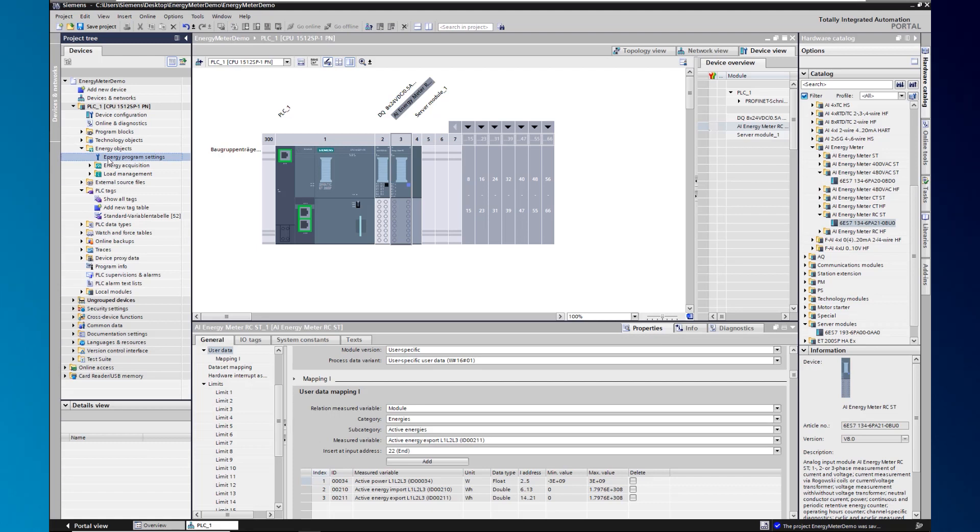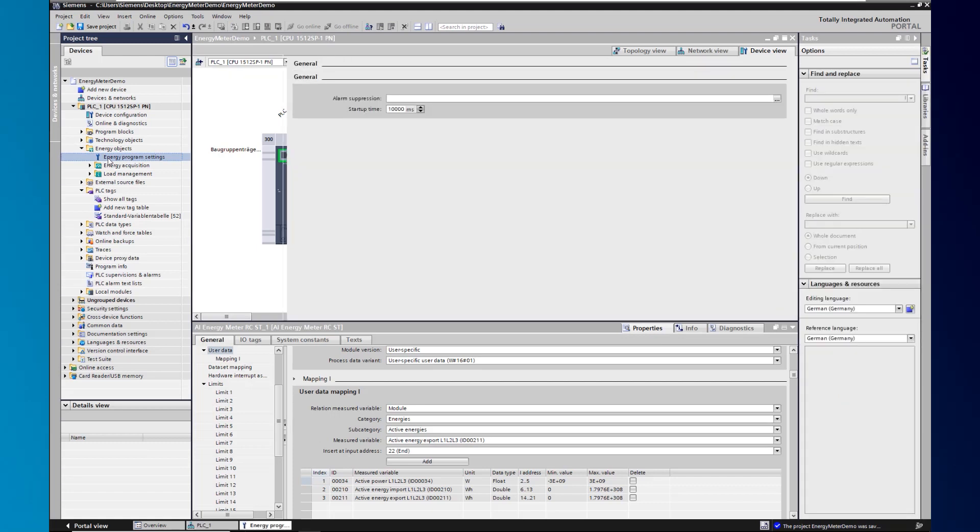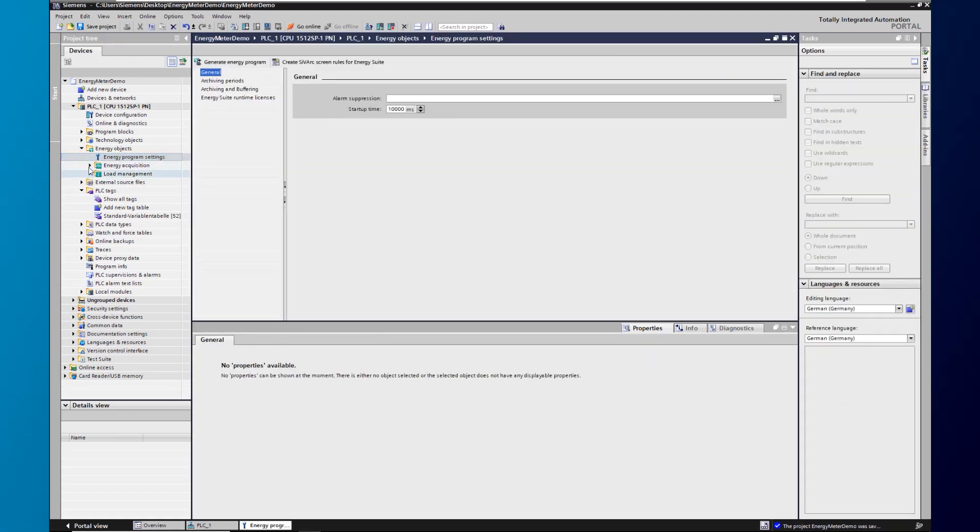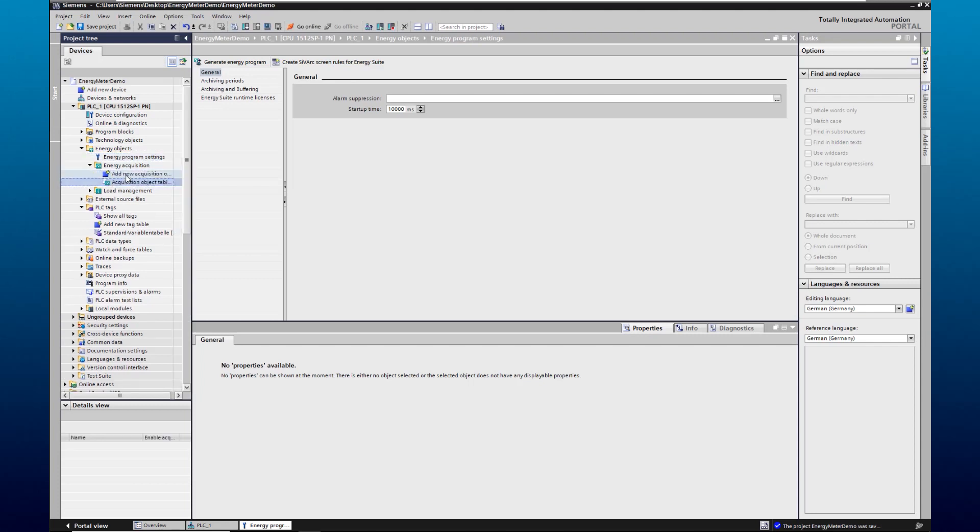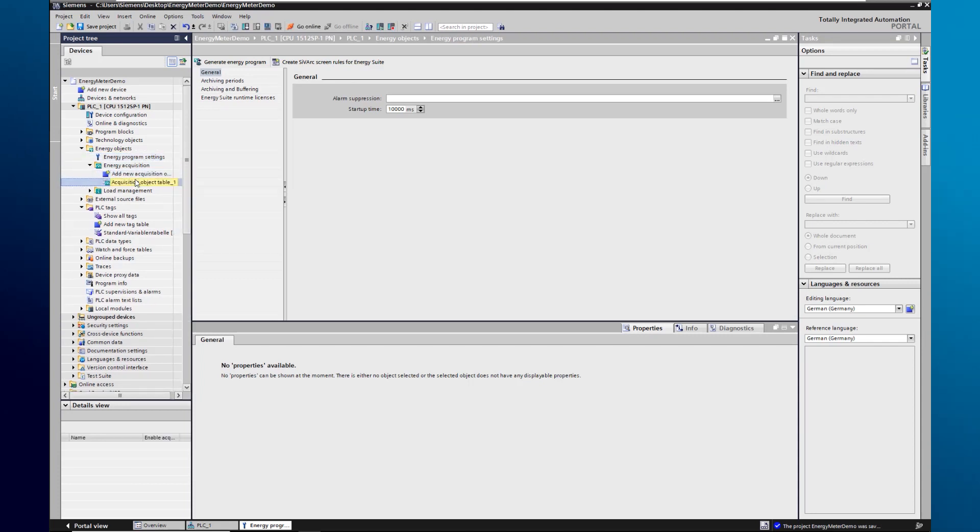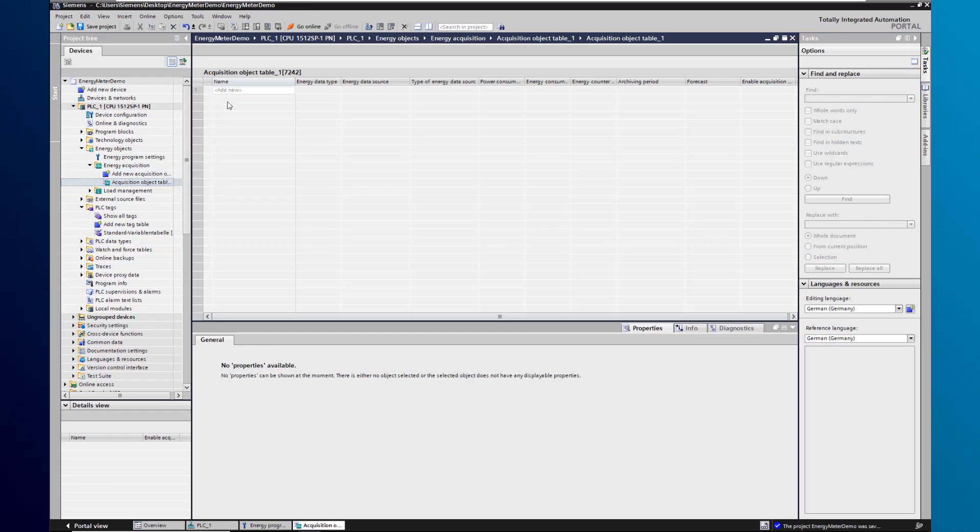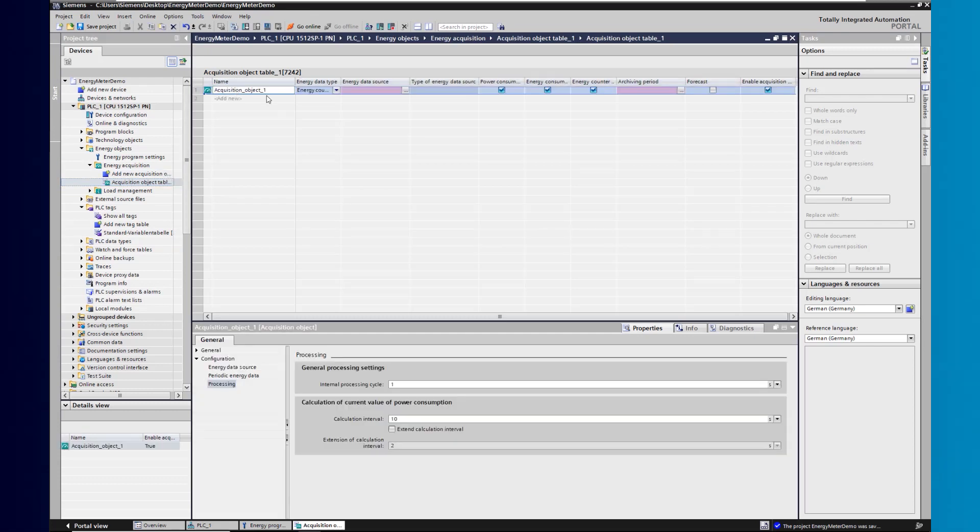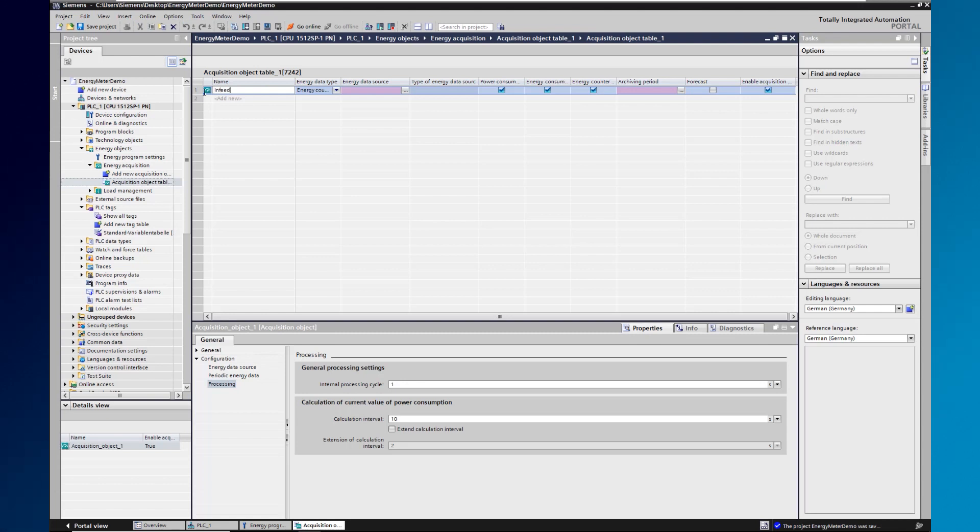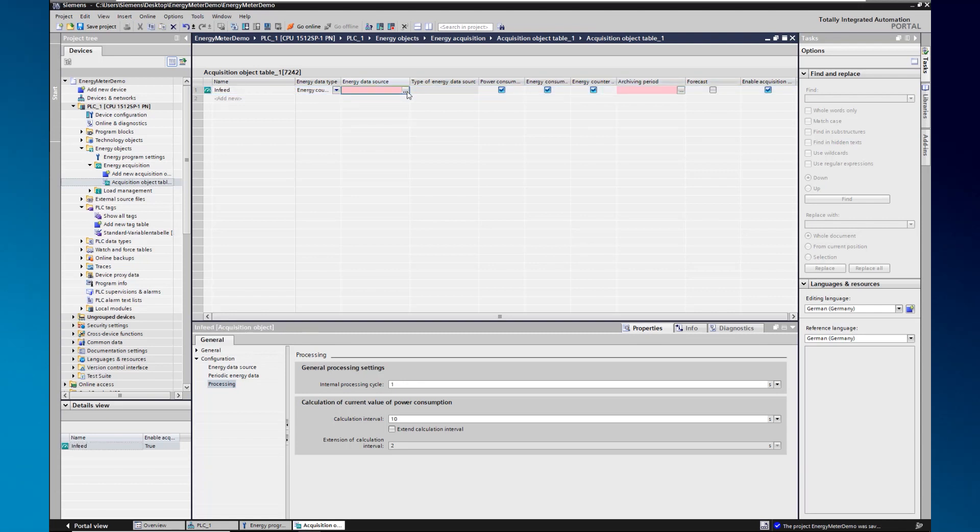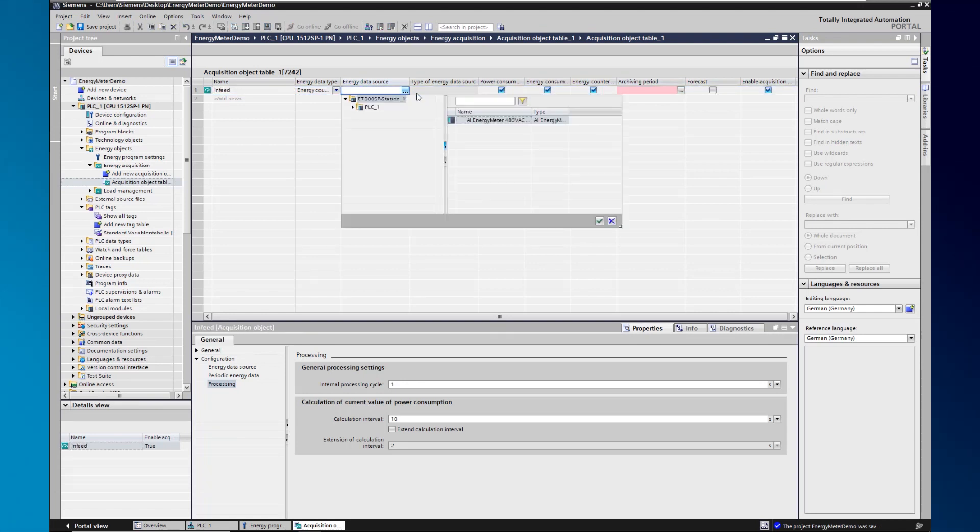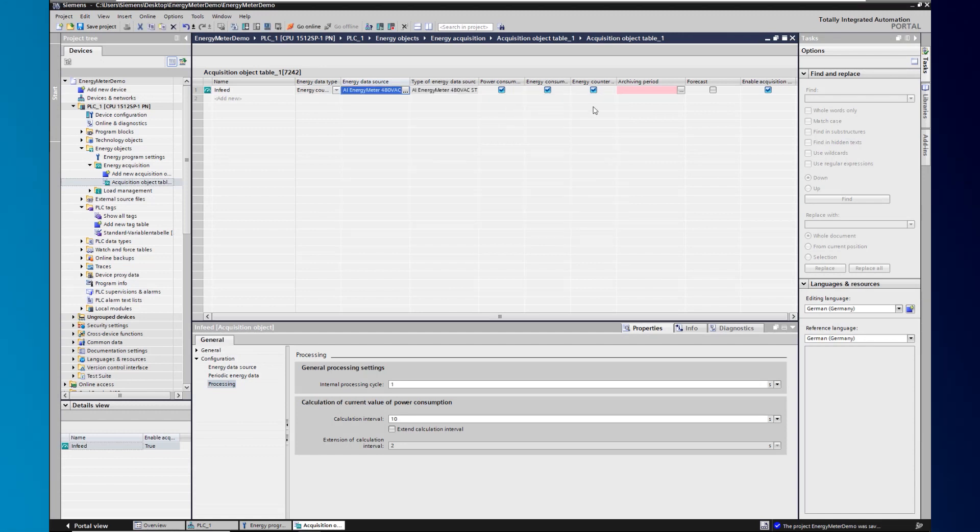To create the energy meter as an energy data source for an energy object, navigate to energy objects within the PLC. Create a new energy object table and a new energy object. Then choose a name for the energy object and select the energy meter as energy data source.